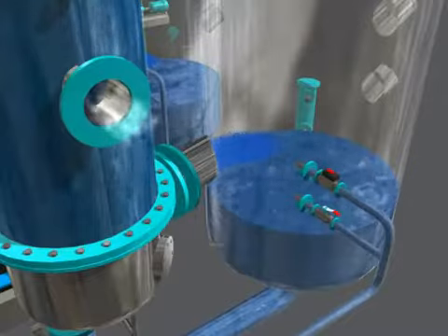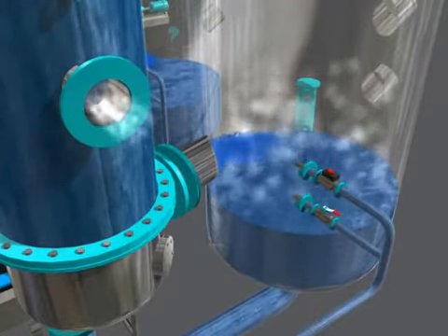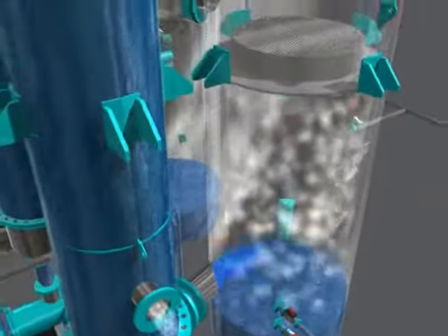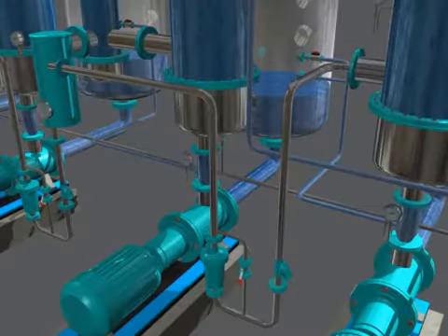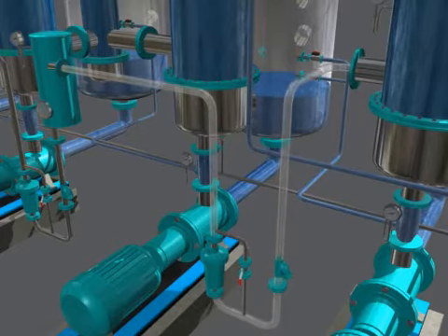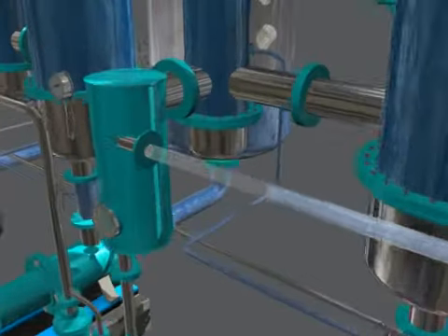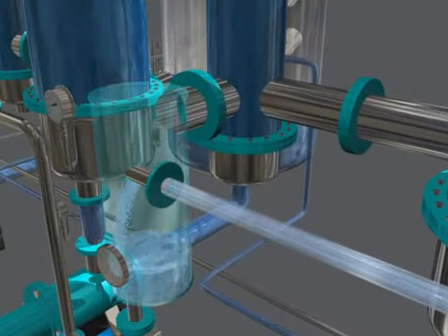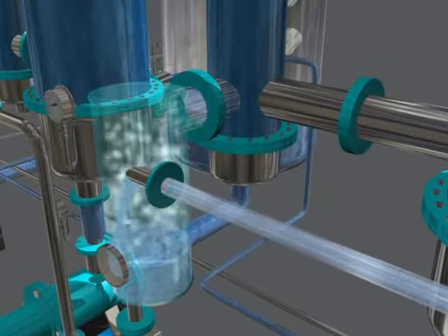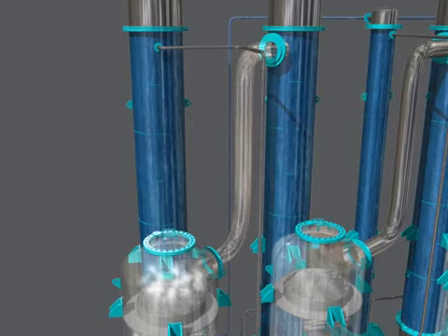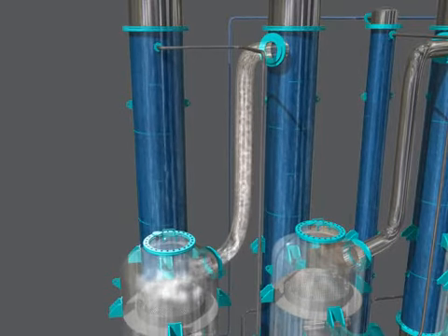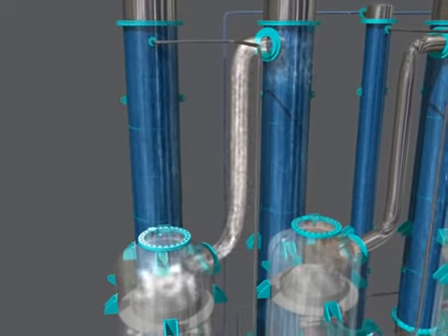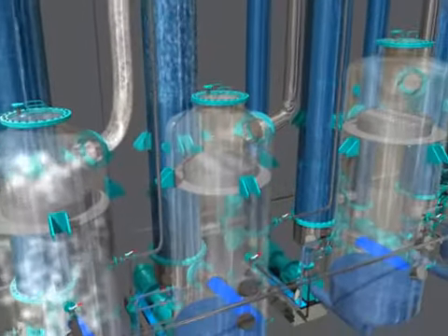Start supply of steam to the heater at the required pressure. The feed gets heated and flashes in the vessel due to lower pressure. Preheaters use the flash vapors of the hot condensate to preheat the feed close to the boiling point, thereby saving steam. The vapor generated by flashing of the liquid is taken to the next effect due to the lower pressure and used for evaporation in the next stage.